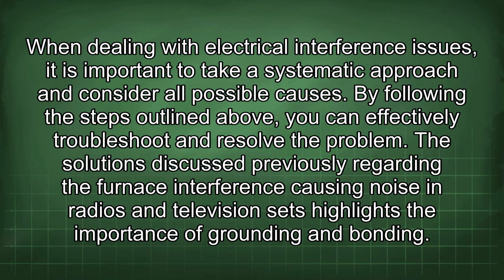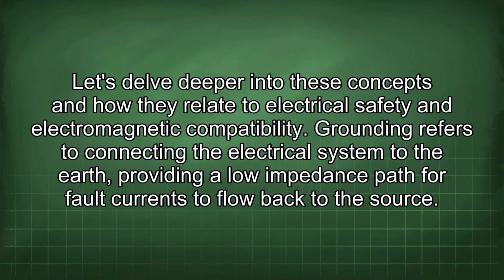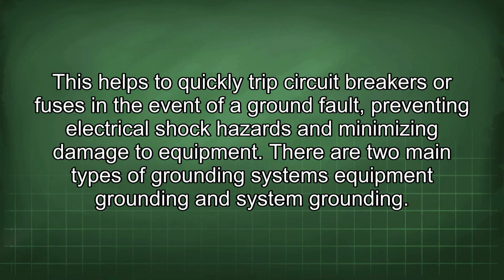The solutions discussed previously regarding the furnace interference causing noise in radios and television sets highlight the importance of grounding and bonding. Let's delve deeper into these concepts and how they relate to electrical safety and electromagnetic compatibility. Grounding refers to connecting the electrical system to the earth, providing a low impedance path for fault currents to flow back to the source. This helps to quickly trip circuit breakers or fuses in the event of a ground fault, preventing electrical shock hazards and minimizing damage to equipment.